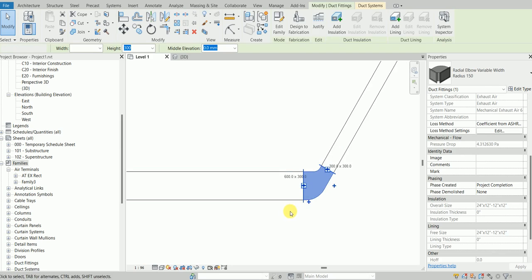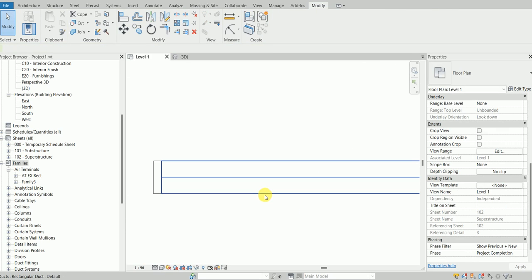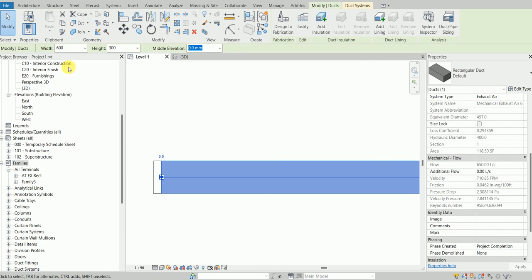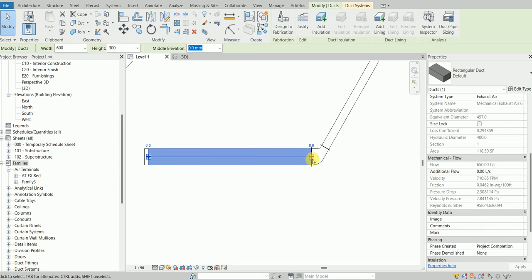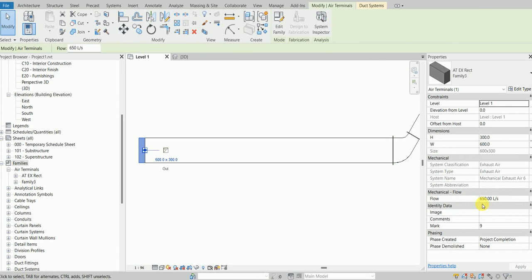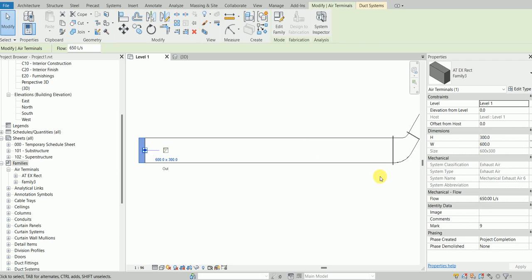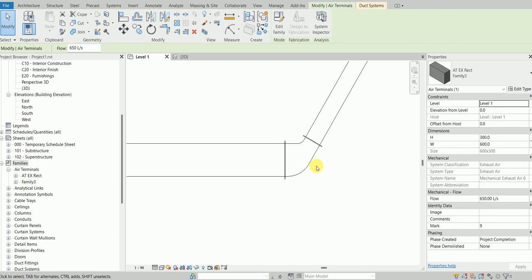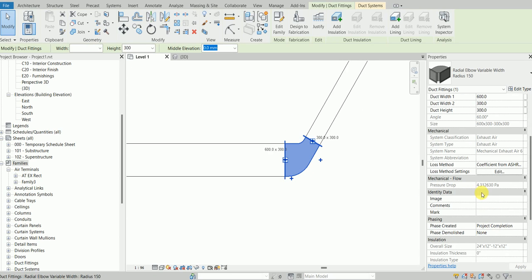This size is 600 by 300, and the angle is 60. The flow rate I set was 650. I'll put 650 and calculate. It's giving me 5 pascals, which is kind of the same as 4 pascals here.